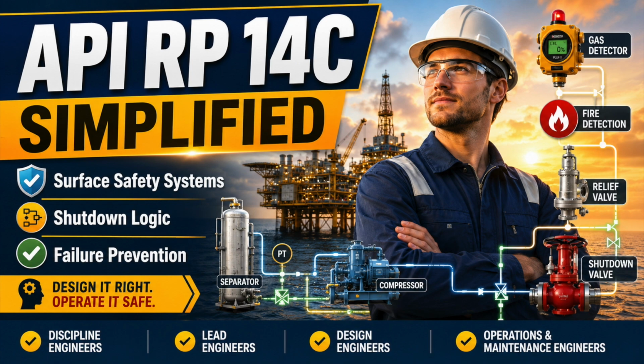Shutdown valves can fail. Actuators can move slowly. Instrument gas can be lost. Impulse lines can plug. The pressure can rise faster than predicted. Thermal expansion can continue even after every process flow is isolated. Heat exchanger tube rupture can expose a low-pressure section to a high-pressure source. Fired equipment can continue adding heat. Relief capacity and discharge routing must address the actual governing scenarios.